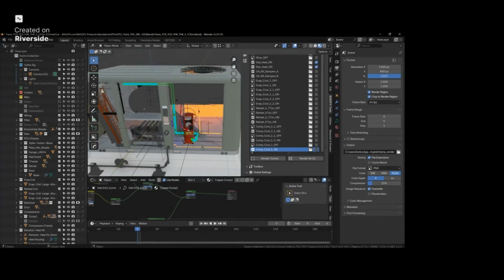Just like I'd do for a chilled water coil or a modulating gas valve, I'll do the same for heat. Even though it's single-stage electric heat that's either on or off, I'll still give you 0 to 100% in increments of 10, just for giggles, because it lets the image work either way -- if it's false you choose 0, if it's on you choose 100. Or it might be a two-stage gas valve, where 30% or 50% is your first stage, without having to add another heat exchanger -- some of these units may have two-stage gas valves.